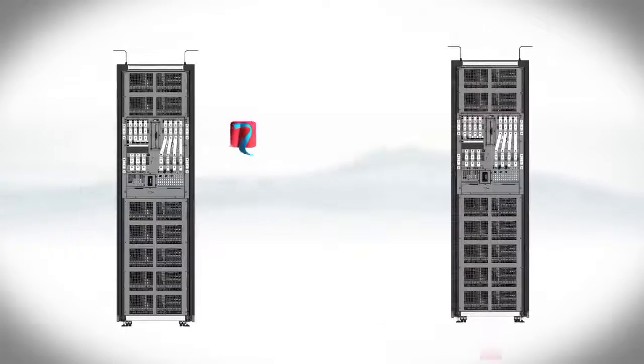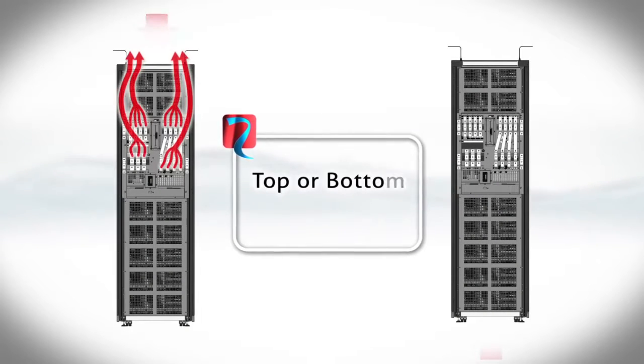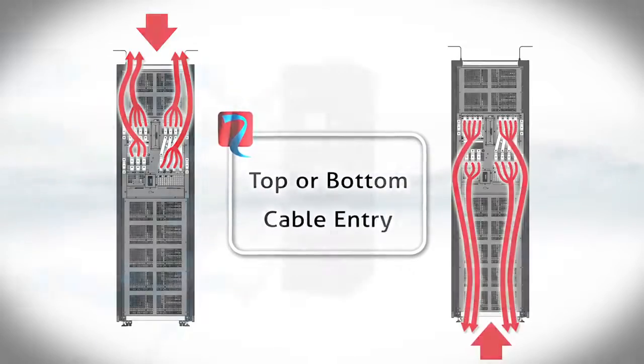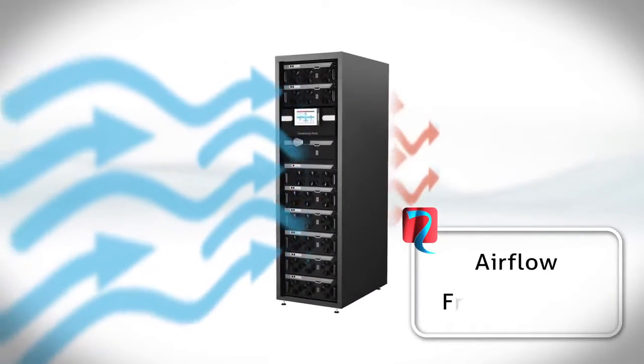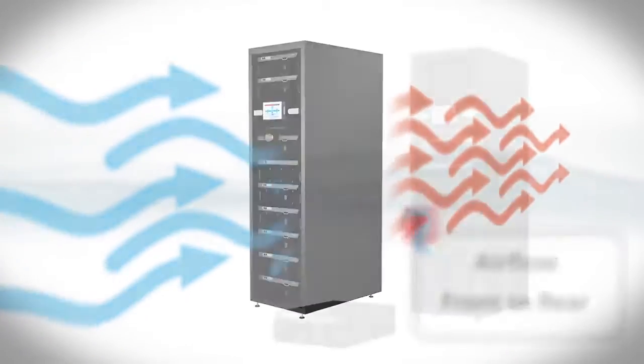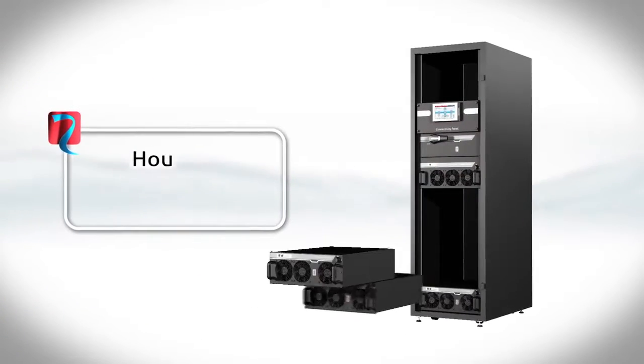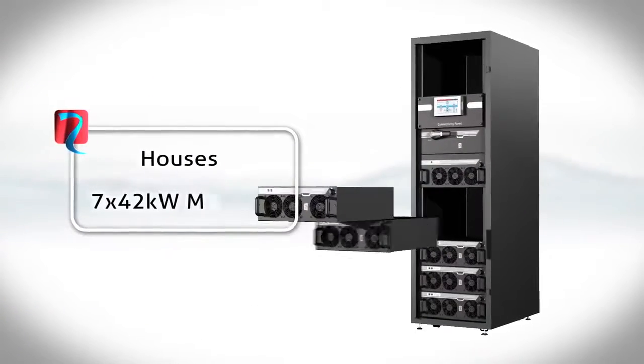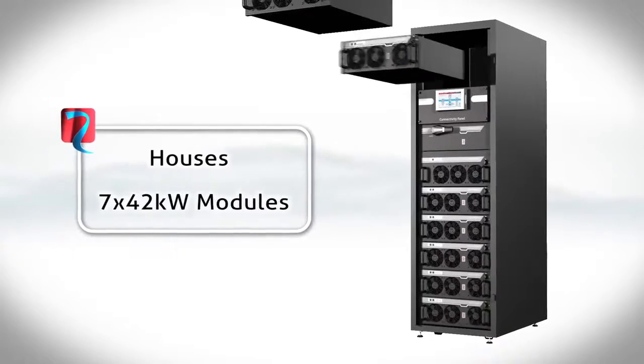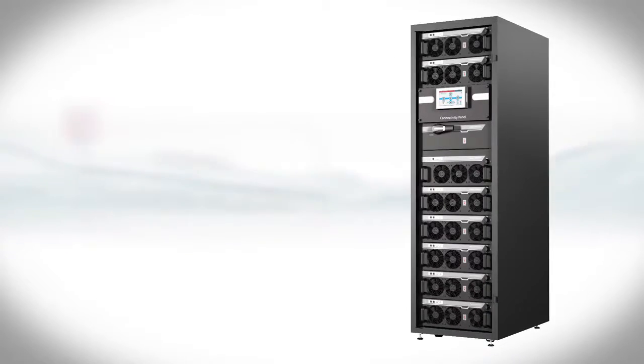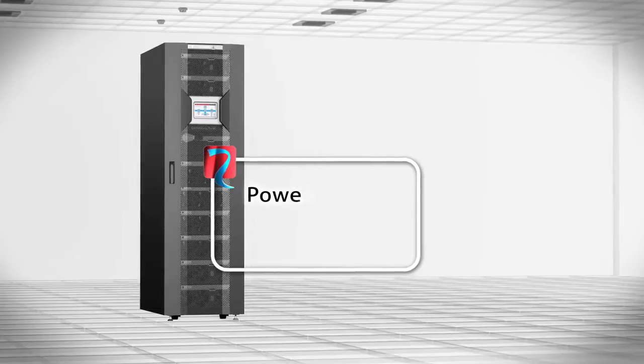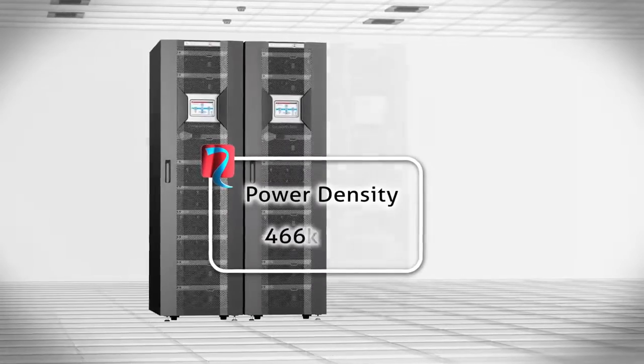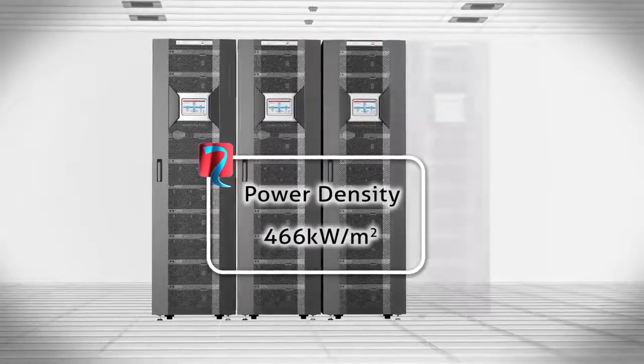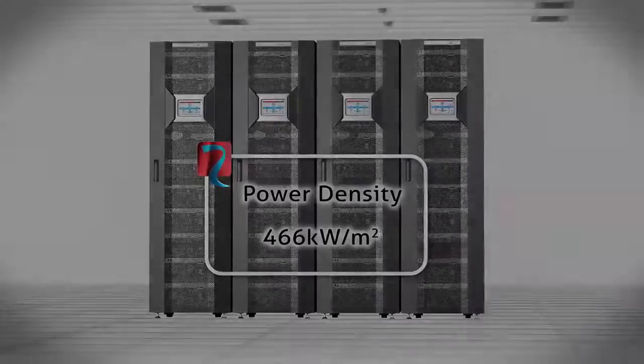Multi-power initial installations are easy and painless, with top or bottom cable entry, plus airflows like server racks, which are front to rear. Data centers grow, so the multi-power needs to grow with it. With the ability to house 7 42 kilowatt modules in one cabinet, and up to 4 cabinets in parallel, delivering over 1 megawatt, giving it one of the highest power densities in the market at an incredible 466 kilowatts per squared meter, including redundancy.